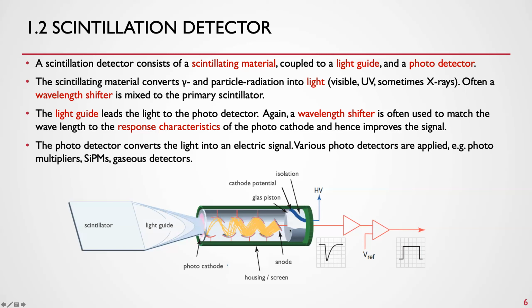So that's a photomultiplier. It needs a high voltage supply because one needs a large electrical potential, a large electrical field between the various screens here. And then there is an amplifier. Okay, so the light guide is supposed to lead the initial scintillation light towards the photocathode. It's not the only thing that it's doing. Typically, the material properties of the scintillator determine the frequency and the wavelength of the light that's produced. That's clear.